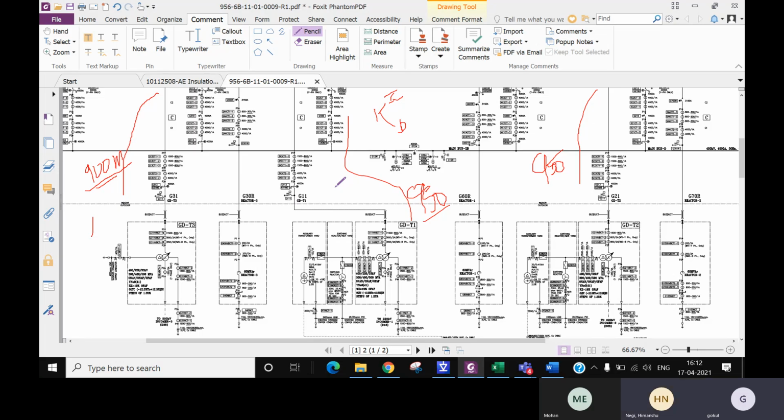Even I read in one of the theses that they have done the ferroresonance in ATP, which you have shown, right? Yes, ATP. They have done it in that also. EMTP is the right tool for that, either ATP, EMTP-RV or PSCAD. Sometimes some clients may ask you to do the ferroresonance study also. You can't do that in other software like DIgSILENT or PSS/E or ETAP. But PSCAD is the right tool because it will be kind of user friendly for you.